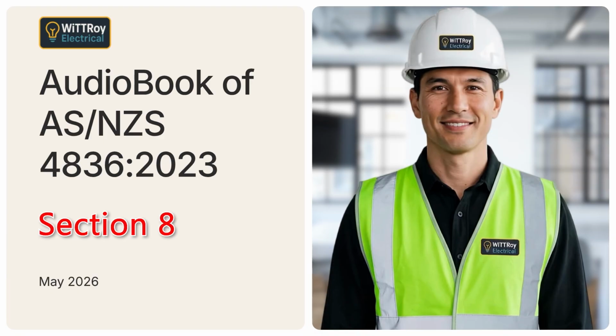Clause 8.3. Portable electric tools. Clause 8.3 introduces portable electric tools. Portable tools are common on electrical work sites. They may include drills, grinders, saws, lamps, test equipment, and other powered equipment. These tools can create electrical risk, especially where there is damage, dampness, construction work, concealed wiring, or contact with exposed conductive parts. So, the tool, the supply method, the protection device, and the work environment must all be considered.